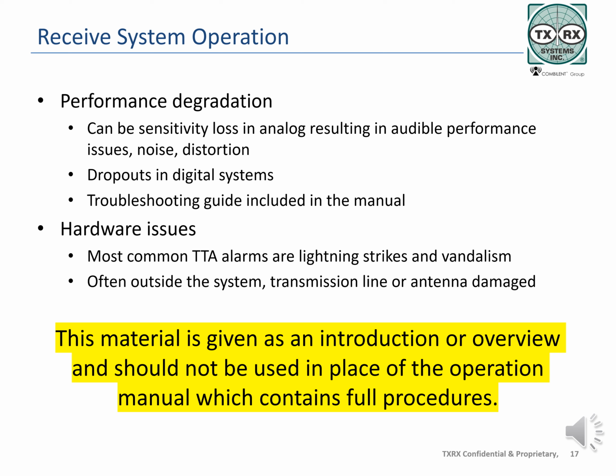System performance is usually at its best following site commissioning and degrades from there. As discussed in other training modules, nothing improves with time on a tower. Performance degradation shows up as loss in range, loss of received sensitivity, audible noise in FM systems, and dropouts in digital systems, known as cliff effect. If you are seeing a sensitivity loss on a continuous basis, it is more likely to be an equipment or hardware issue and should be investigated. Two of the most common sources of hardware issues resulting in TTA alarms are vandalism and lightning strikes, resulting in transmission line or antenna damage, failed lightning arresters, or other physical damage to the system.